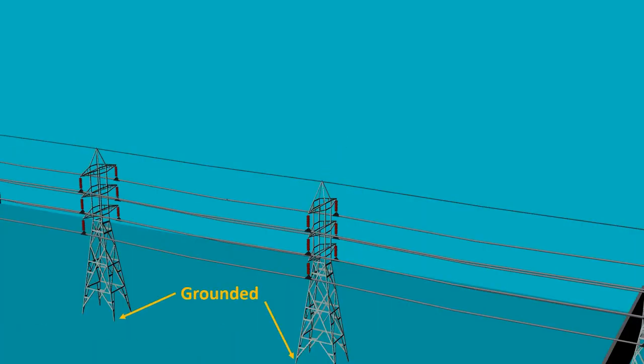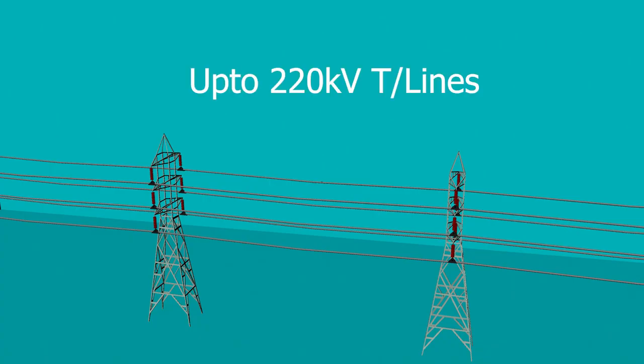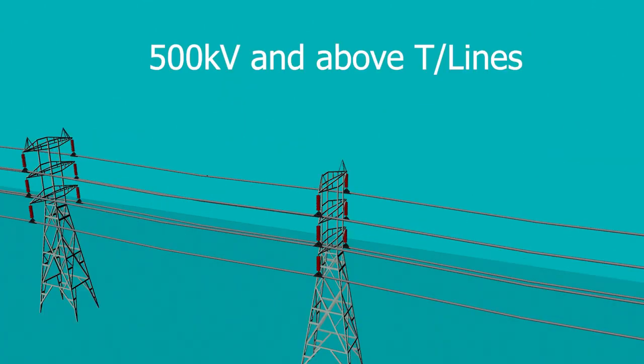Unlike the phase conductors that are isolated from the tower through disc insulators, the earth wire is connected to each tower of the transmission line and each tower is properly grounded using earth rods of specifications as per international standards.